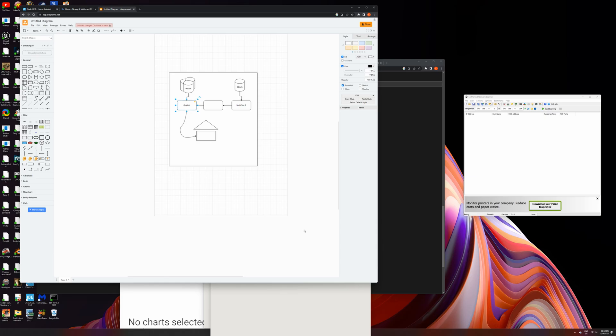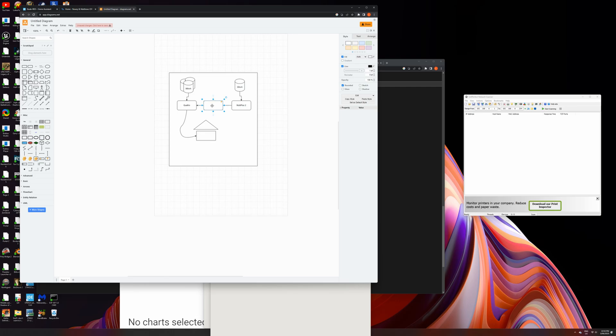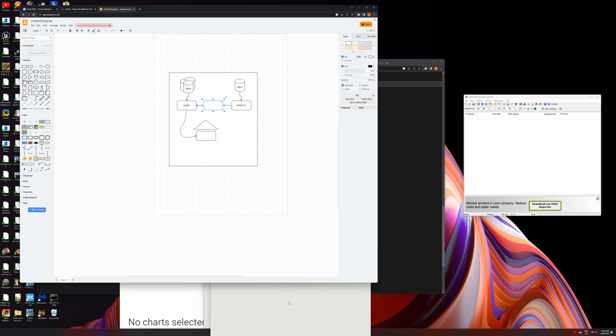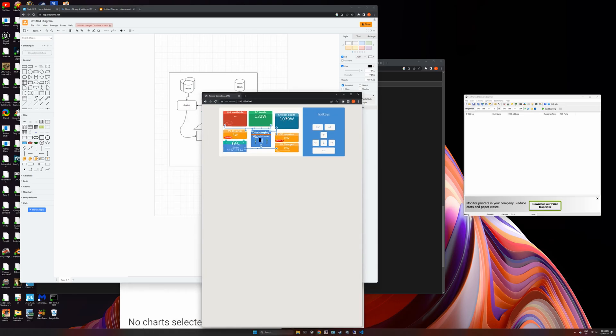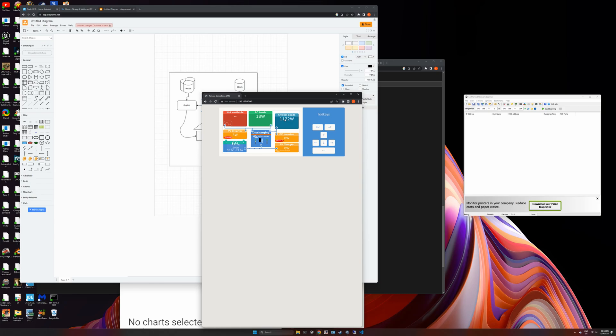The other thing about that is that our readings are being obscured now because the Quattro is completely unaware that the multi-plus two is having an impact. The danger is also, we've got so much AC coupled solar that there's a danger that the multi-plus two might overcome the Quattro's ability to deal with surges. So there's a rule that you're supposed to stick to that you will not commission more than one-to-one ratio of VA on your inverter versus watts on your PV. And for all intensive purposes, the multi-plus two has become an AC coupled solar here, right, that this Quattro is completely unaware of. And that in itself has got dangers. So I wouldn't recommend this solution to anybody. I just thought it was an interesting experiment and felt that it was worth sharing.